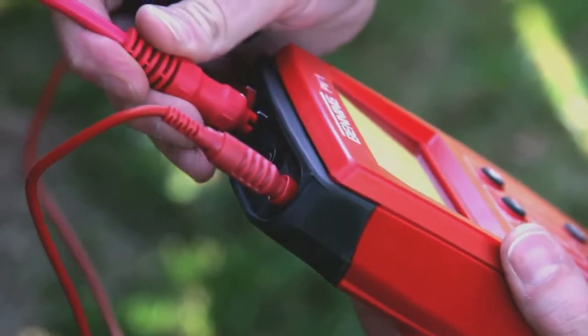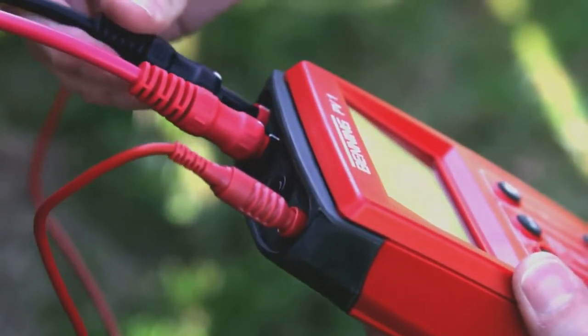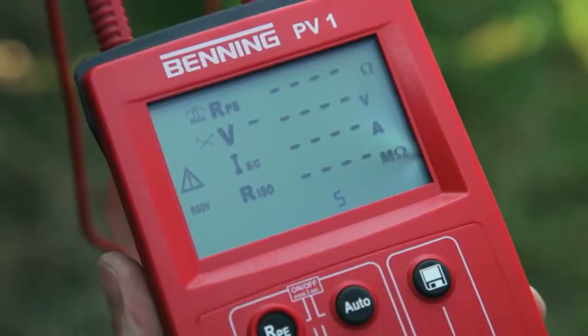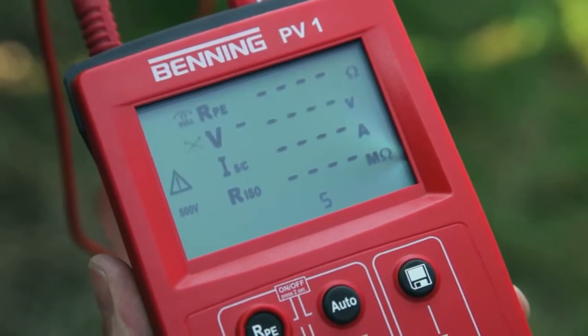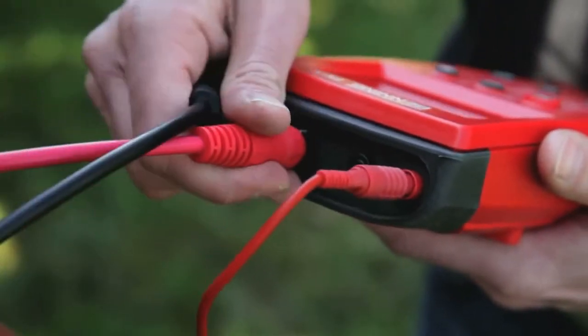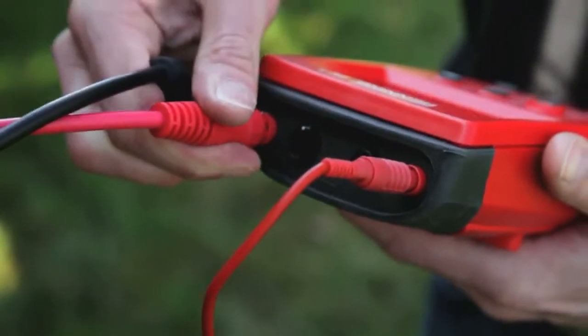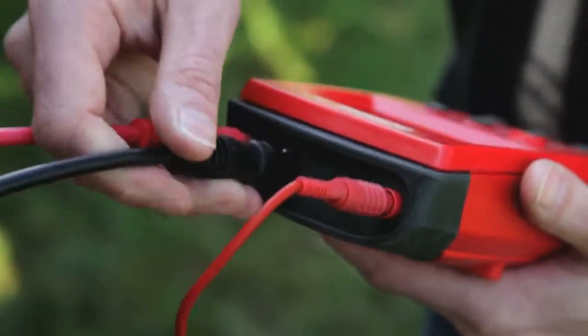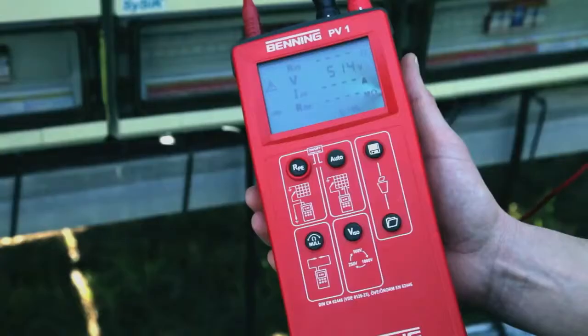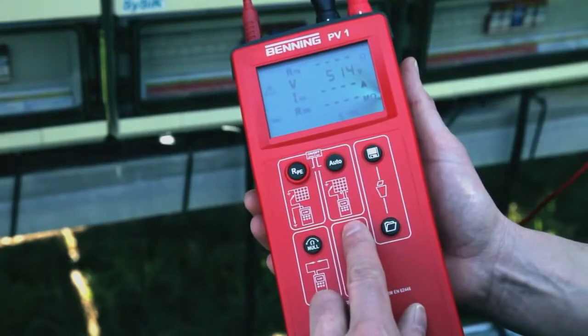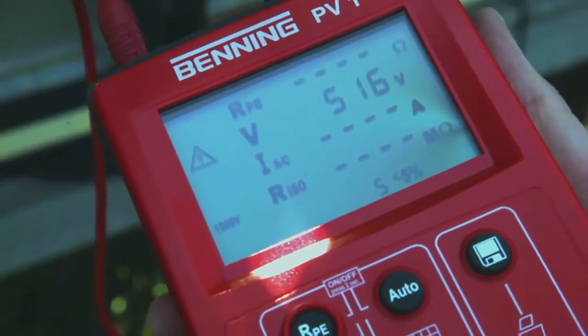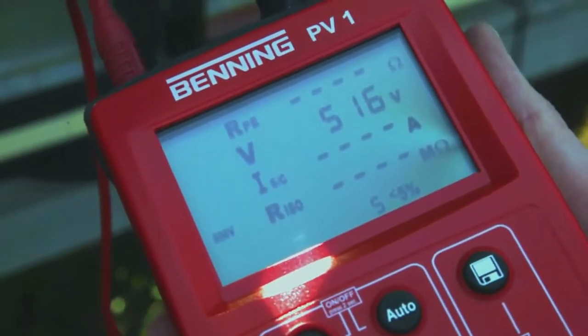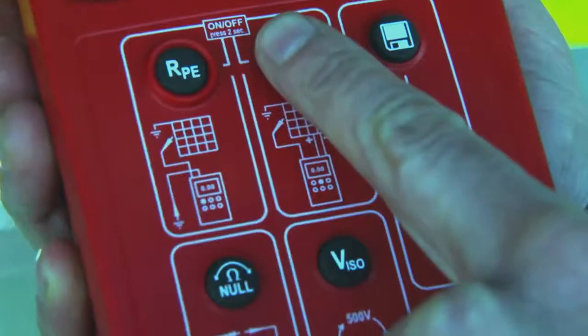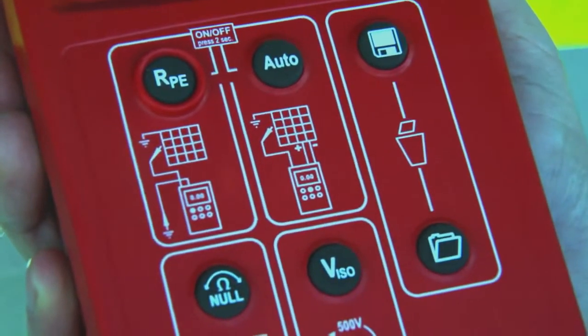The Benning PV1 automatically detects reversed polarity, shows it on the display, and the further measuring process is blocked. In case of correct connection, the PV1 automatically displays the open circuit voltage. After having selected the appropriate testing voltage for insulation measurement, here 500 volts, press the Auto key to start the fully automatic test sequence.